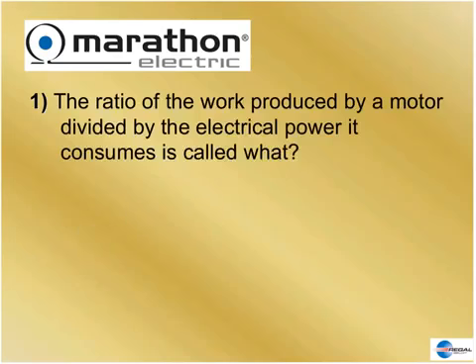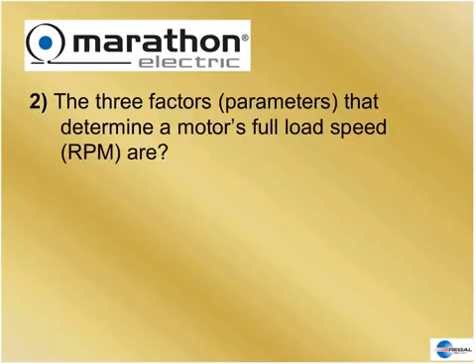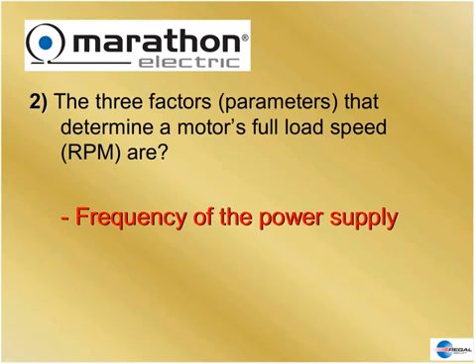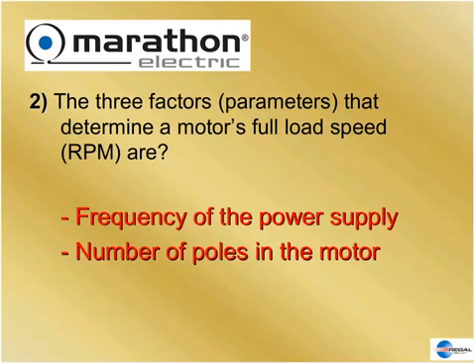Three factors determine the motor's full load speed: the frequency of the power supply, the number of poles in the motor (poles always come in pairs — you can't have an odd number), and the amount of slip. The slip is the torque — it produces the torque and requires the torque. Those three things determine motor speed.